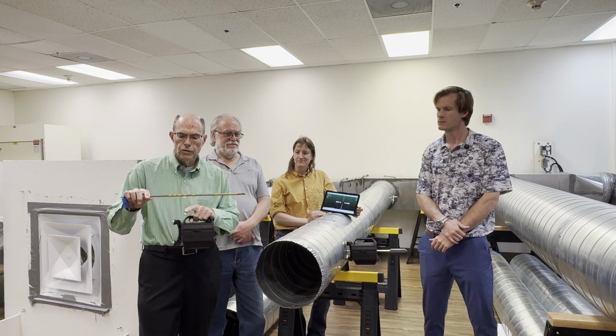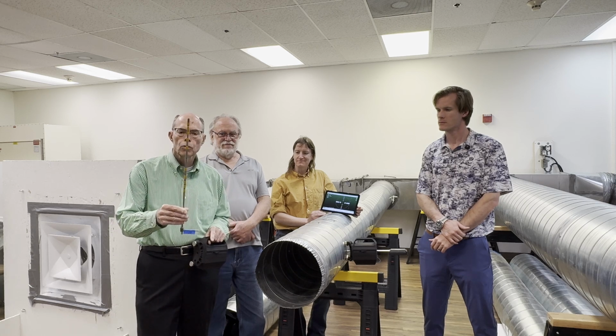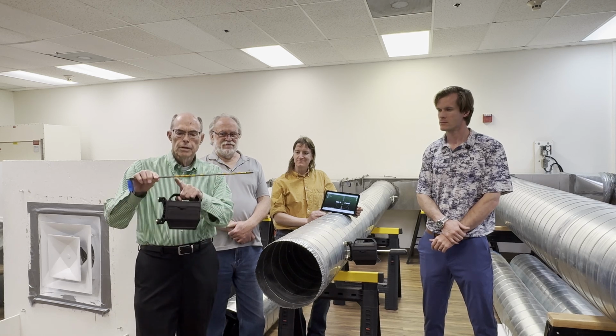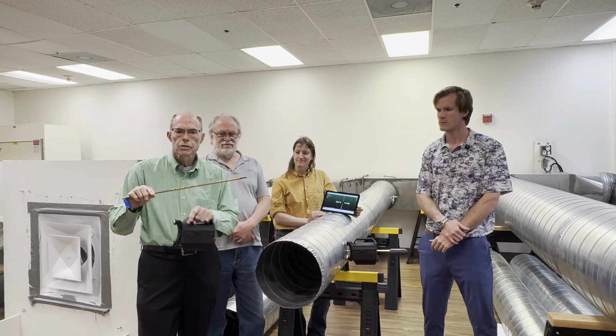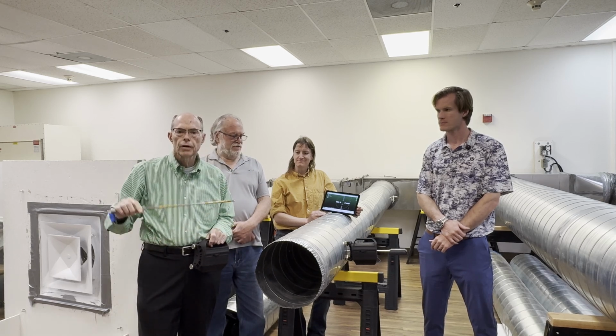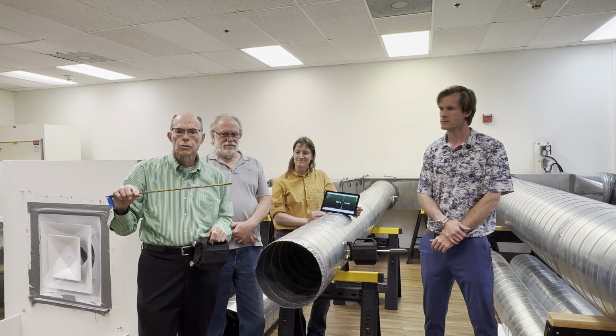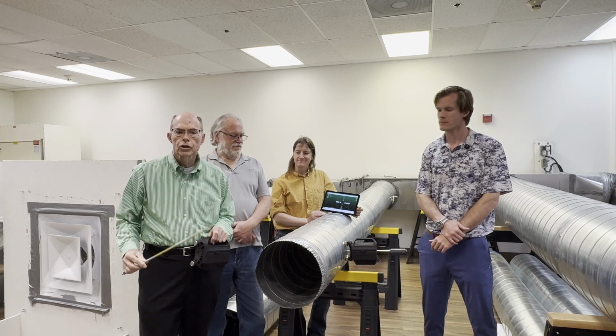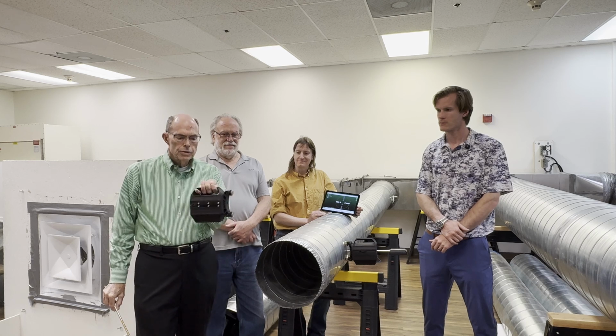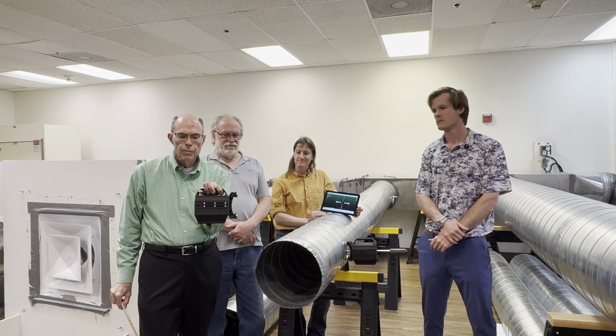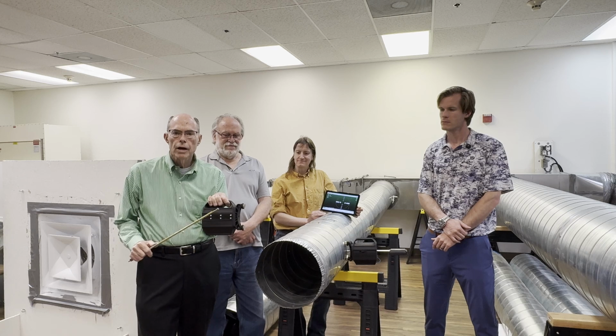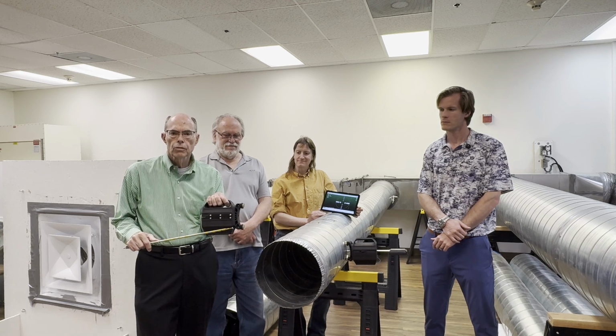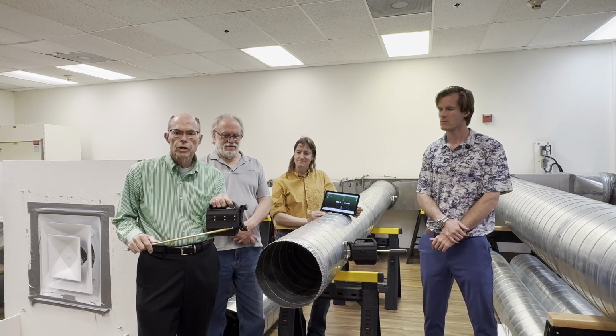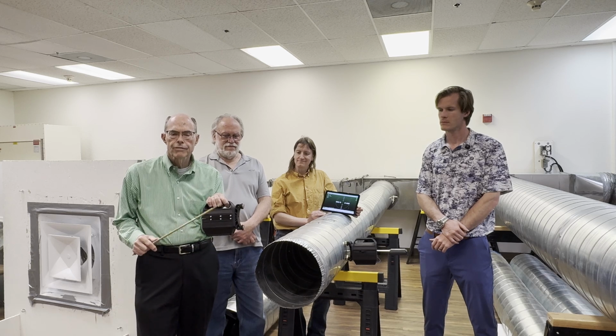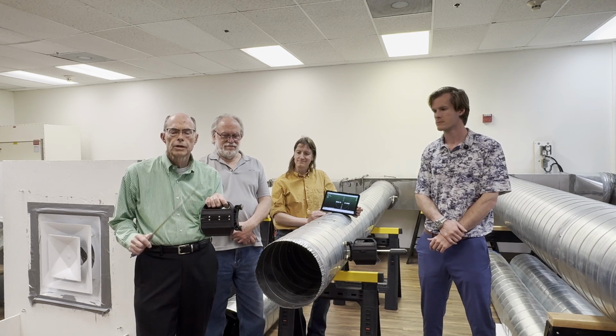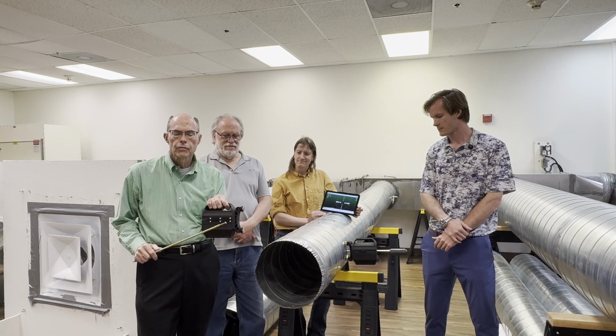Typically with a duct traverse, you'll use a foil probe like this or a pitot tube like this. You mark the depth locations and insert it through a hole in the duct, making a measurement at each location to come up with an average velocity. This machine is portable, battery operated, and has a motor that drives a shaft to the appropriate locations, making a measurement at each one and calculating the average velocity and CFM exactly the same way every time.